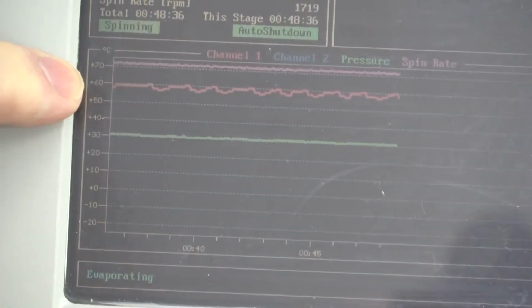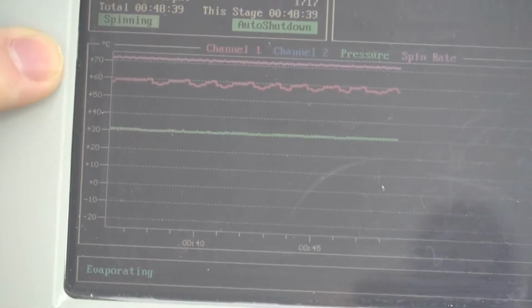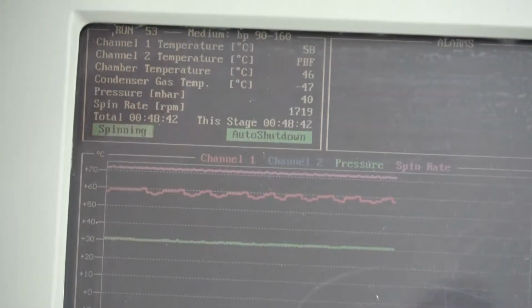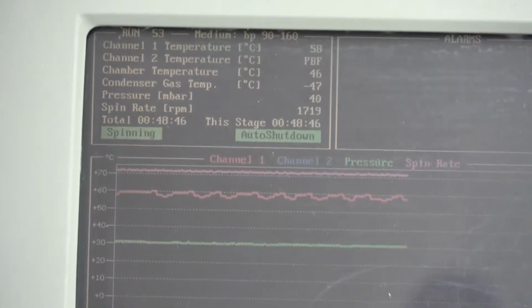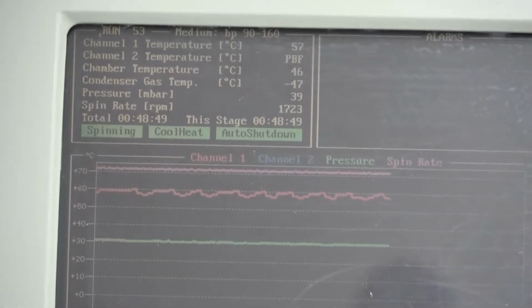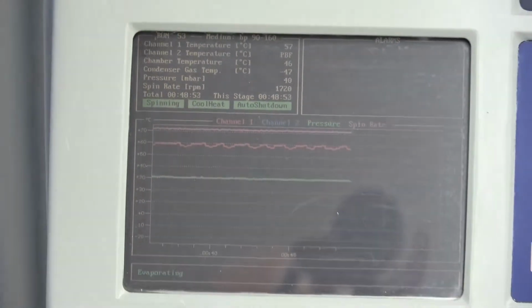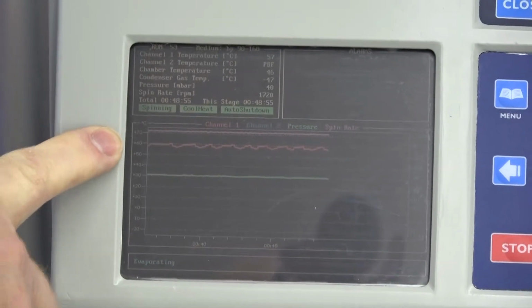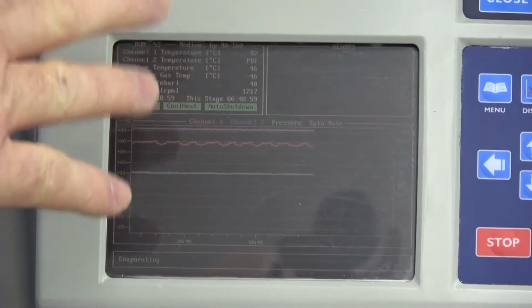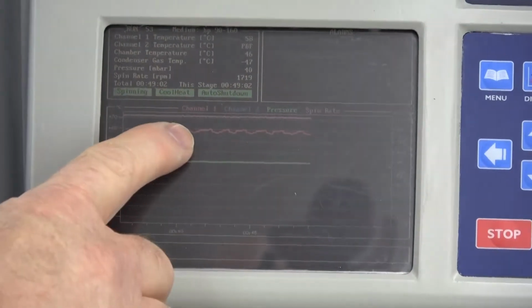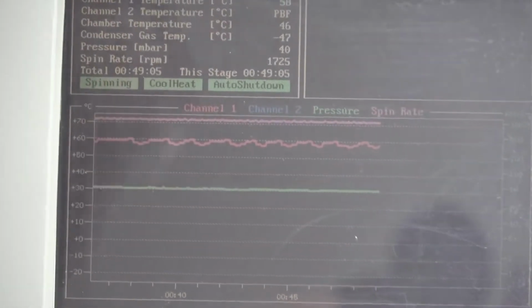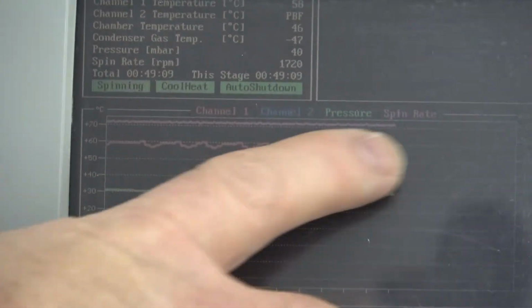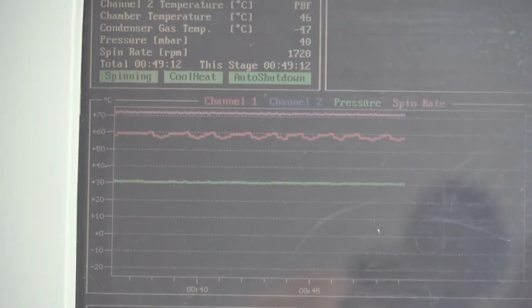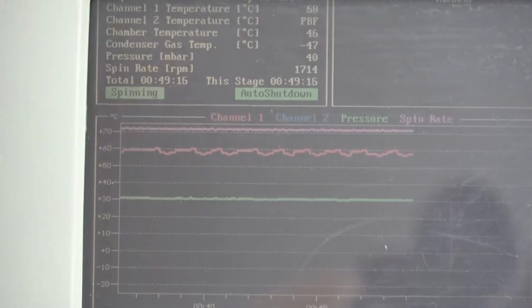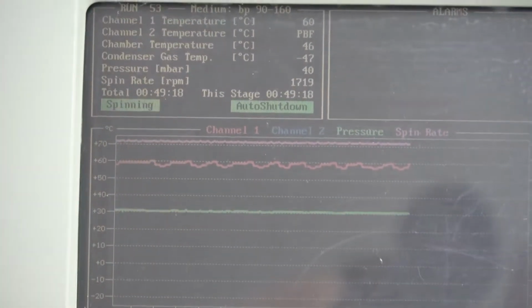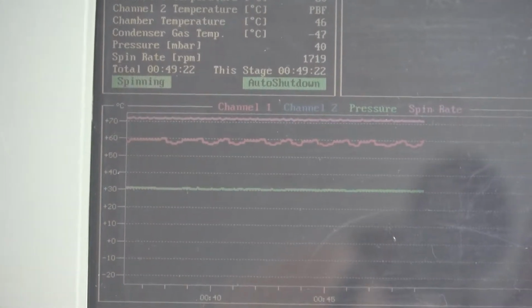And then the next line is the actual CoolHeat. This is an option that the Genevacs have where it actually monitors your samples. Not only is the system monitoring the chamber inside, it also has a couple ports where it monitors the actual sample and the spinning trays. I think I have it set around 60 degrees Celsius, so you can see the line kind of bouncing up and down. It kicks on and off and fluctuates a little bit, but it's keeping a very consistent temperature for the sample only. So you're keeping a very accurate temperature for the sample as it's being evaporated, especially with those volatile ones that you have.